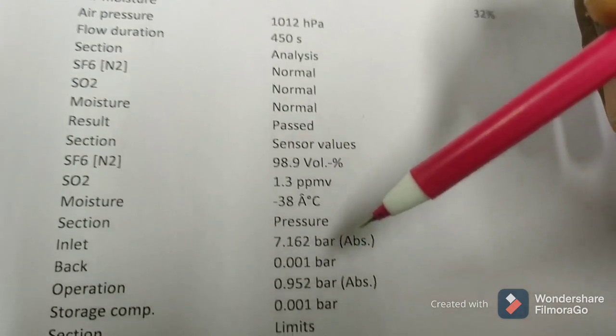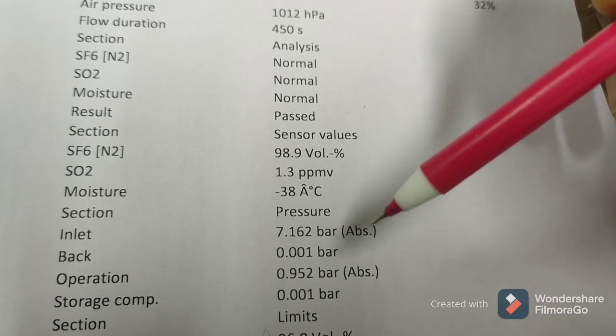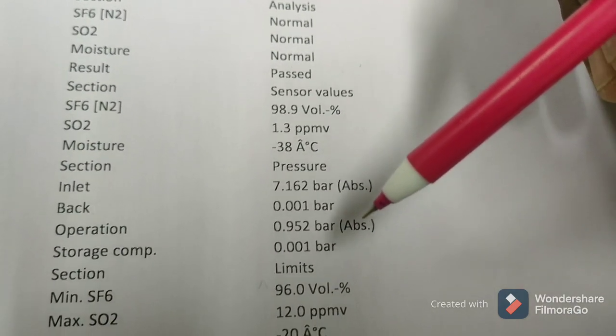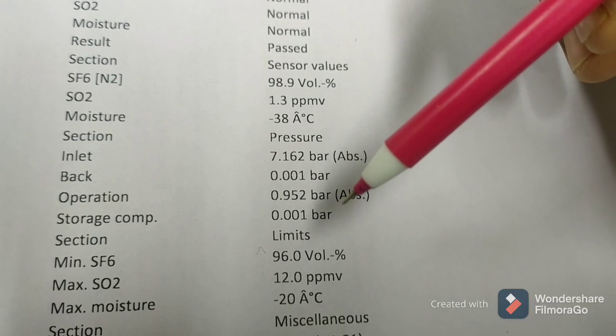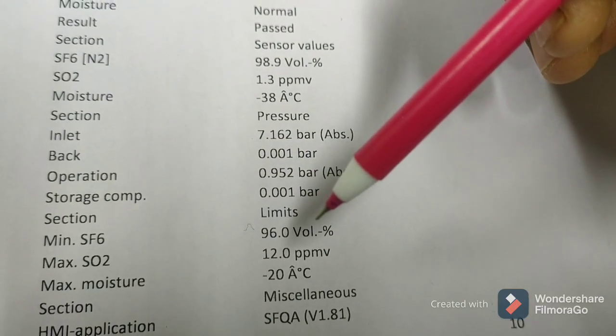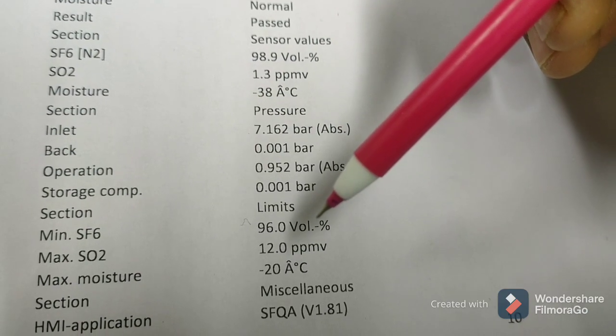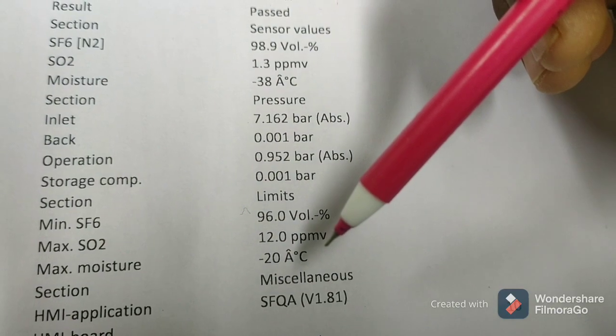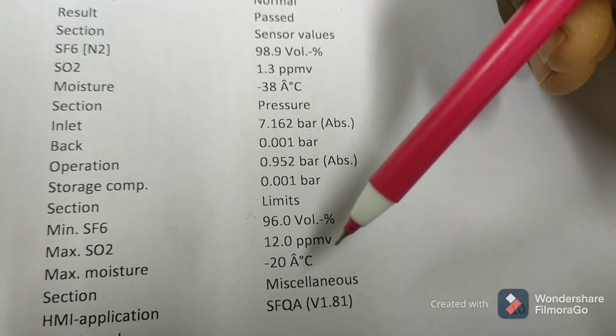The section pressure: inlet pressure 7.162 bar, operation 0.952 bar, storage component 0.001 bar. Minimum SF6 is 96% volume, maximum SO2 is 12.0 ppm, maximum moisture is -20°C.